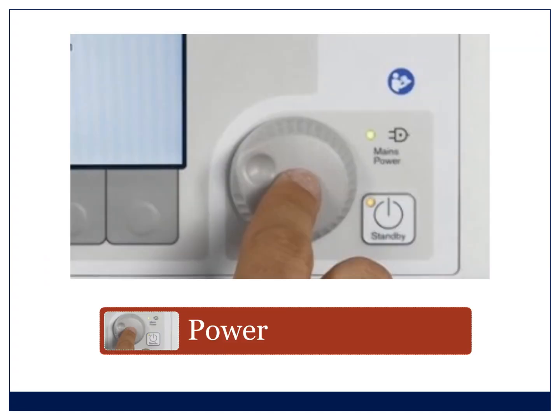So just to go into a little bit more detail, when you're checking the power, you need to know where the light is that says the power is on. And you can see that little green light is there to say you're on mains power. Now, it's quite often the machine is on, but you're actually running on battery power. One of the ways to check it is just to go to the wall, switch the plug off, and then come back and see now what light is showing. But remember to turn the power back on. Make sure you're on mains power and your batteries are charged.